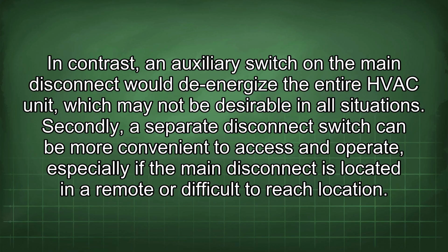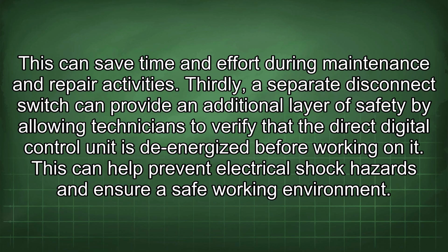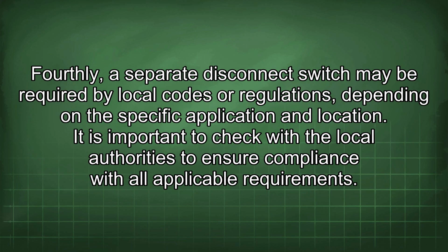in all situations. Secondly, a separate disconnect switch can be more convenient to access and operate, especially if the main disconnect is located in a remote or difficult to reach location. This can save time and effort during maintenance and repair activities. Thirdly, a separate disconnect switch can provide an additional layer of safety by allowing technicians to verify that the direct digital control unit is de-energized before working on it. This can help prevent electrical shock hazards and ensure a safe working environment. Fourthly, a separate disconnect switch may be required by local codes or regulations depending on the specific application and location. It is important to check with the local authorities to ensure compliance with all applicable requirements.